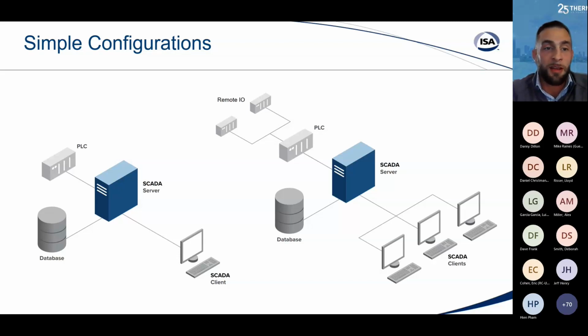Here we just have a single client, but moving to a more spread out architecture, we look at remote I/O connected to the PLC, making it a more distributed system. That same PLC communicates with the SCADA server, pulling its data and logging it into the database, making the data available through multiple SCADA clients in different locations, with multiple operators. It can scale.